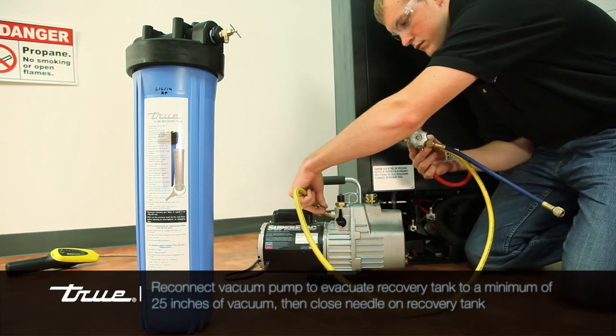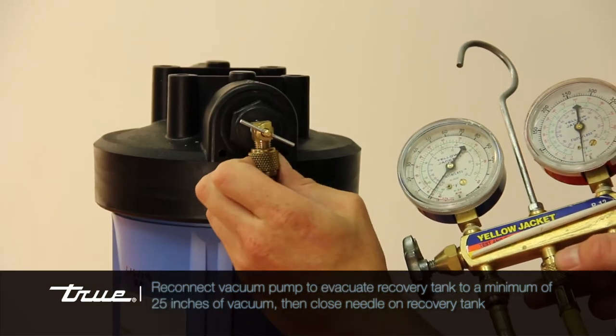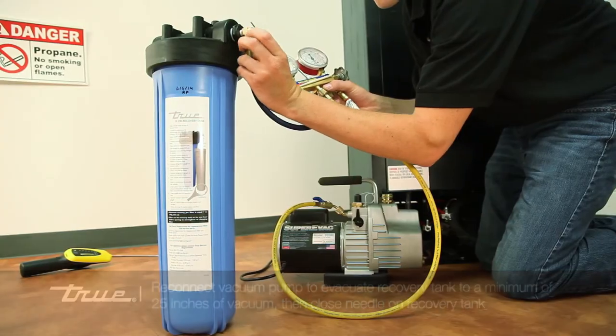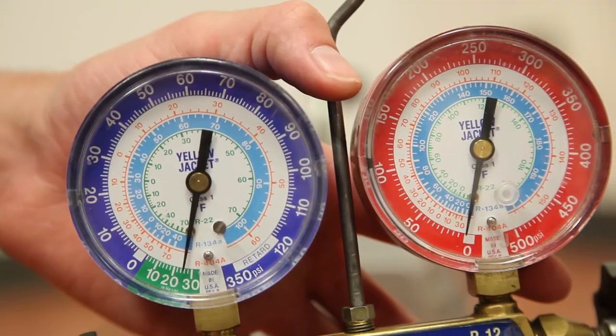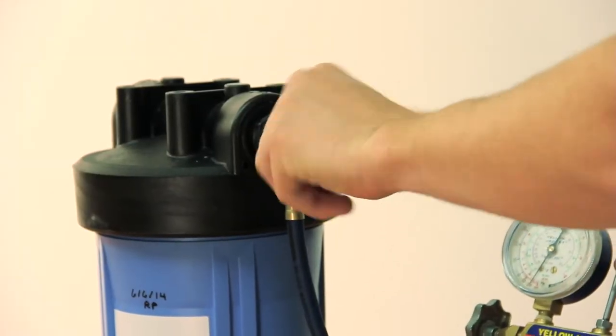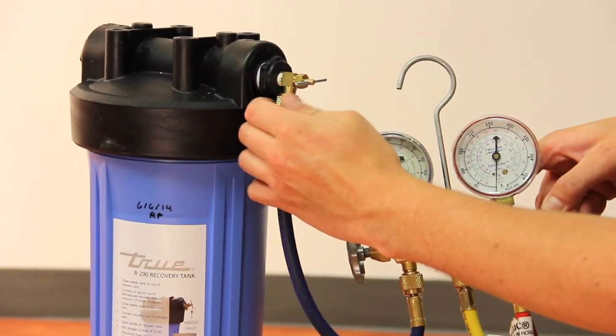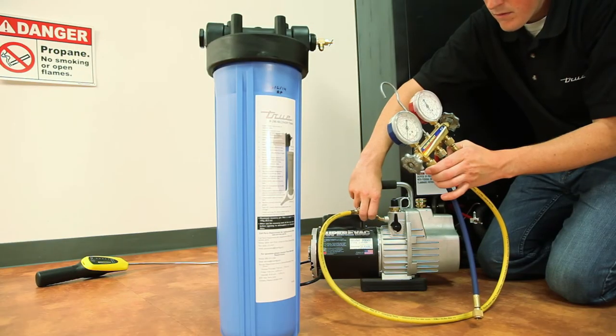Reconnect the vacuum pump and again evacuate the recovery tank to a minimum of 25 inches of vacuum. After a minimum of 25 inches of vacuum is achieved, close the needle valve on the tank along with the knob on your gauges and disconnect the hoses from both the tank and the vacuum pump.